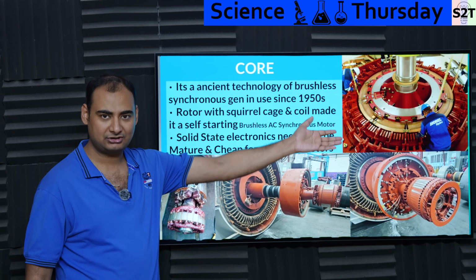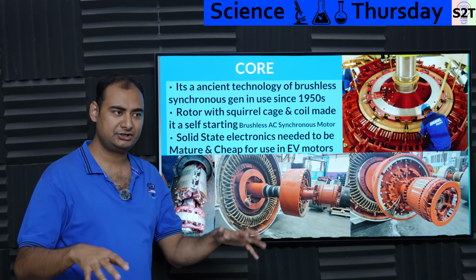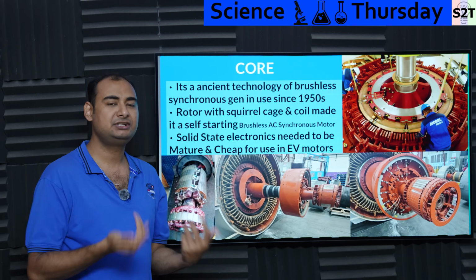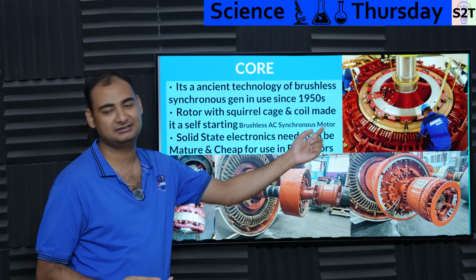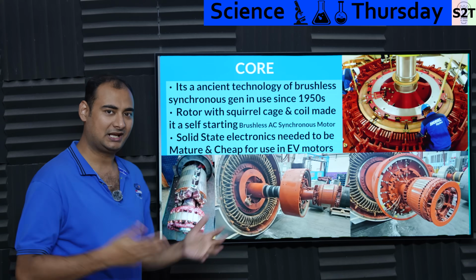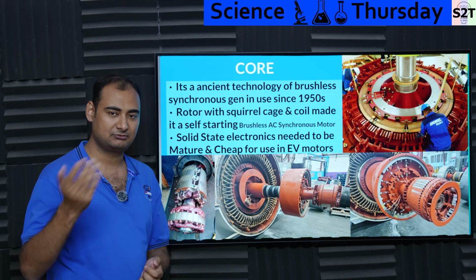So you can control the rotor current - when people put load into it and voltage starts to sag down, you don't need to increase the RPM, you just increase the current going into the system, and voila, you get high voltage. And it goes the other way too.